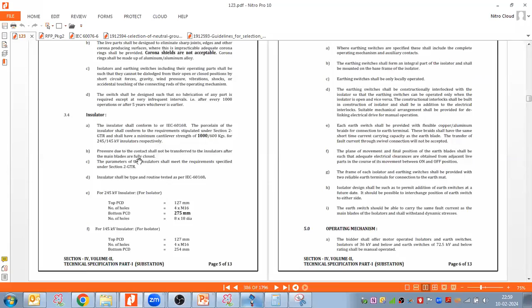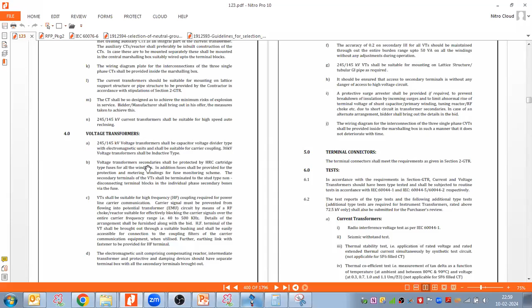So now they are putting the circuit breaker. Anyway, you have to check the site, then the disconnector rating. Please go through and check the site environmental conditions requirement. This is important, since site conditions affect substation designing, including the pollution level. Based on the pollution level, you will decide your phase-to-phase distance, which is very important.